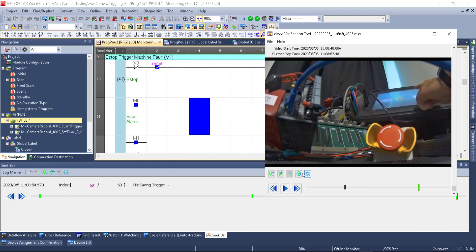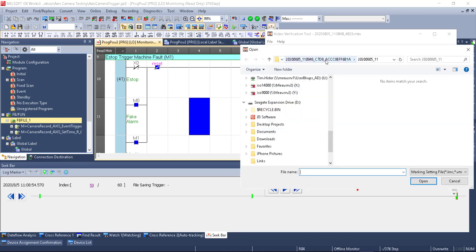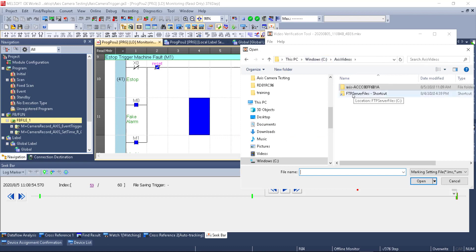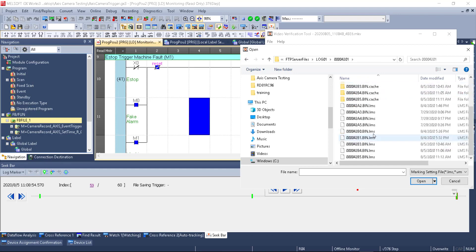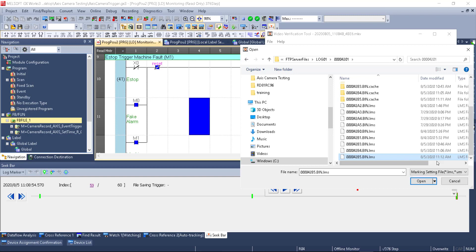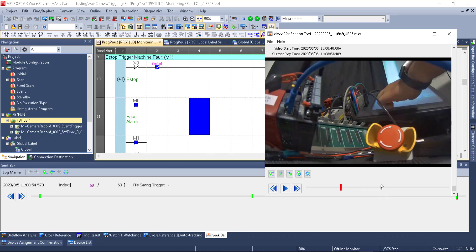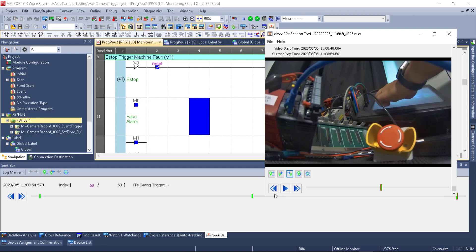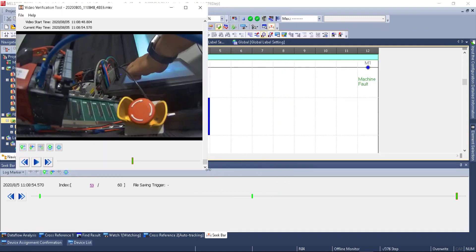Going back to the video verification tool, I delete the existing markers to start with a blank slate. This time I'll read the GX Works 3 log marker file. I navigate to the log folder and find the LMS (log marker) files at the end — selecting the last one created. It's critical to know the timestamp and have the CPU synced with the video file, since you'll be matching date and time down to the second. When I open it, I see all three log markers grouped very tightly together. Clicking through them nothing appears to change visually at this scale.